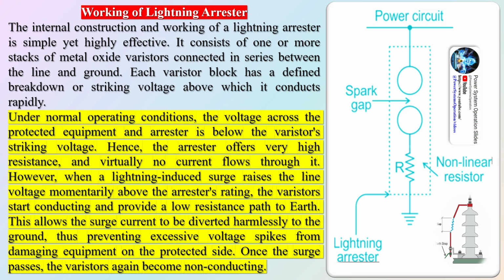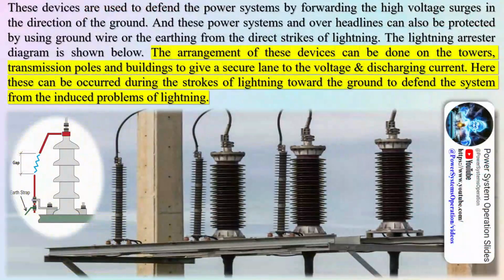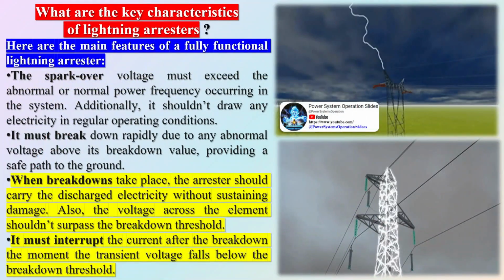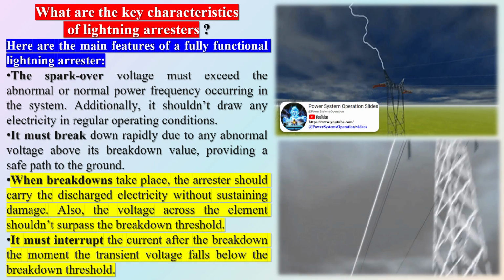The internal construction and working of a lightning arrestor is simple yet highly effective. It consists of one or more stacks of metal oxide varistors connected in series between the line and ground. Each varistor block has a defined breakdown or striking voltage above which it conducts rapidly. Under normal operating conditions, the voltage across the protected equipment and arrestor is below the varistor's striking voltage. Hence, the arrestor offers very high resistance, and virtually no current flows through it.